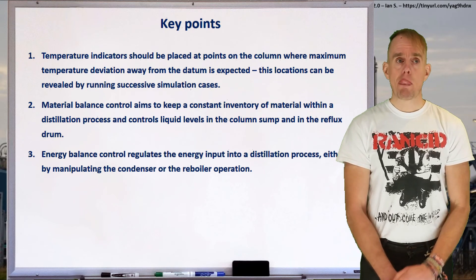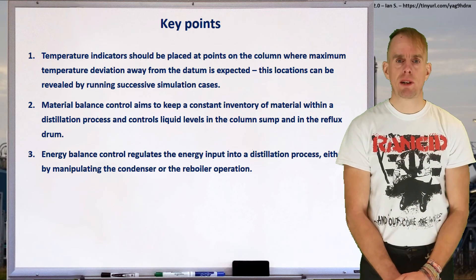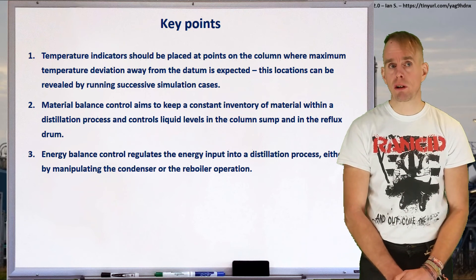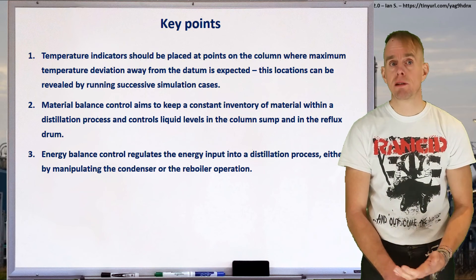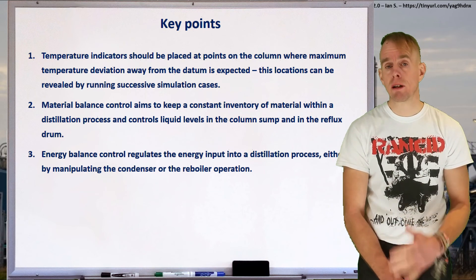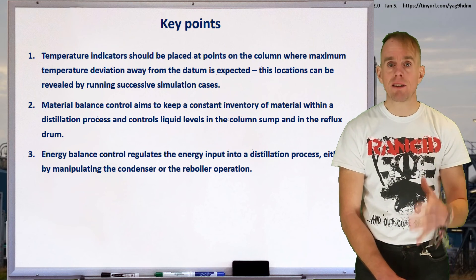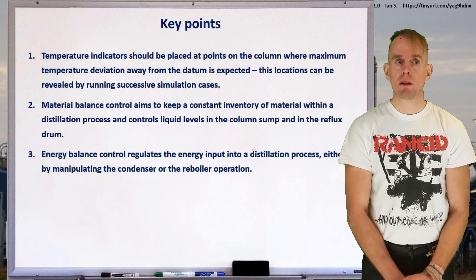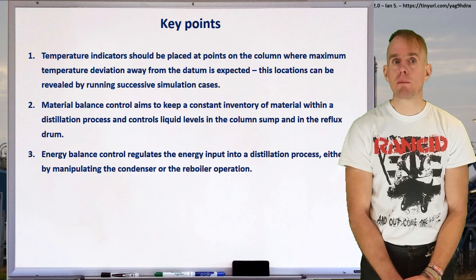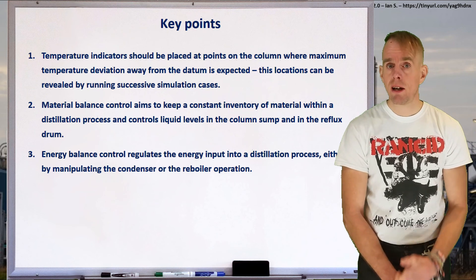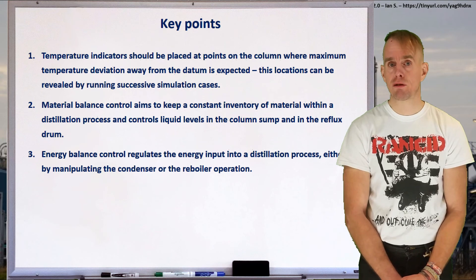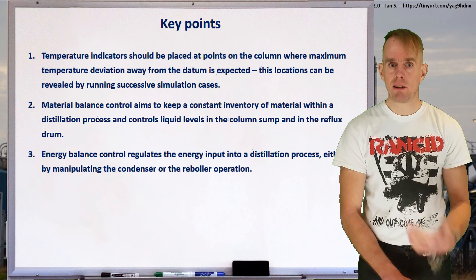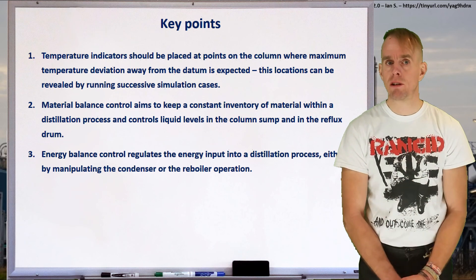Let's recap a few key points. For inferring specification, temperature indicators should be placed at points on the column where maximum temperature deviation away from the datum is expected. These locations can be revealed by running successive simulation cases and compiling the data graphically. We looked at two control schemes: material balance control, which aims to keep a constant inventory of material within the distillation process by controlling liquid levels in the column sump and reflux drum; and energy balance control, which regulates the energy input into a distillation process either by manipulating the condenser or the reboiler.